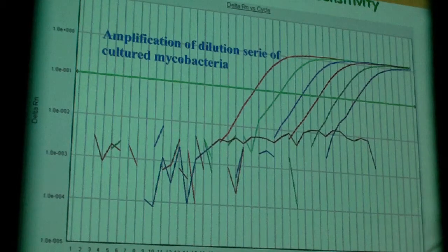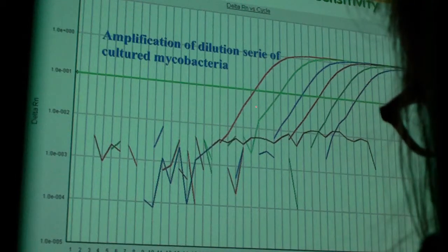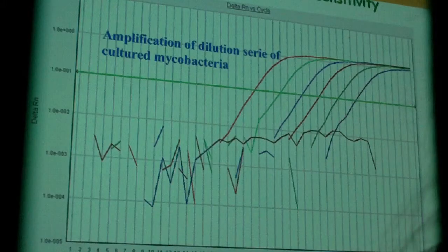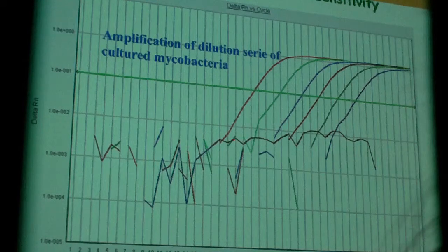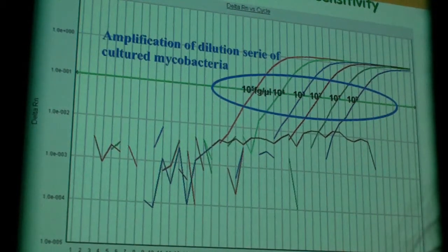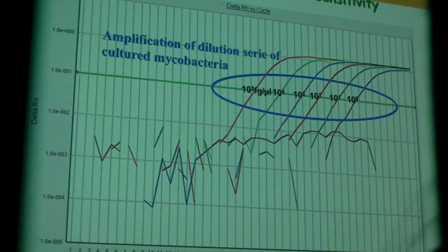What we do for sensitivity is first, when we have this PCR, when you start using it, you want to know if it's really sensitive enough. So you have dilution samples, and you can just take out the concentration until one bacterium is still present, because above this line, the crossing point is a positive signal.